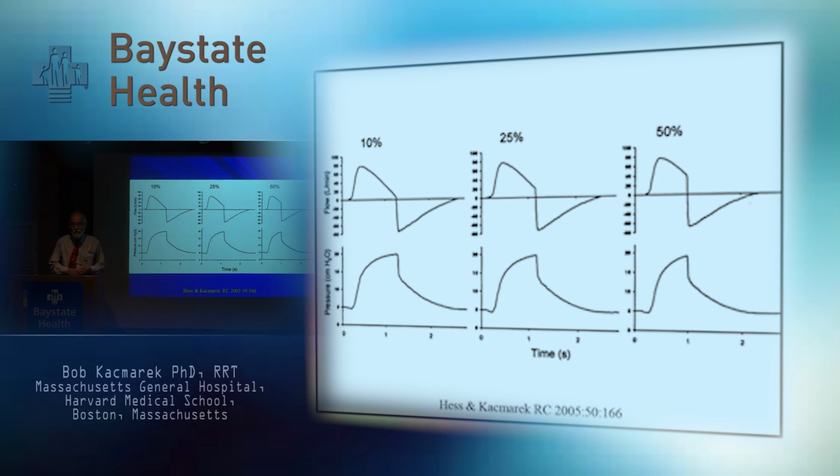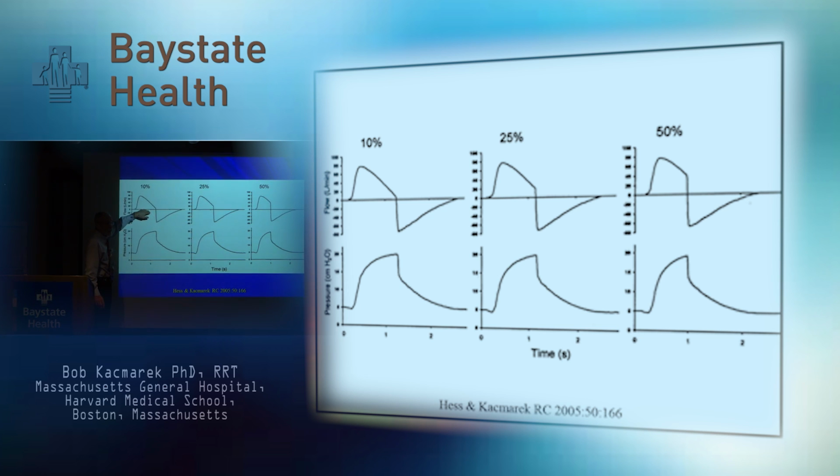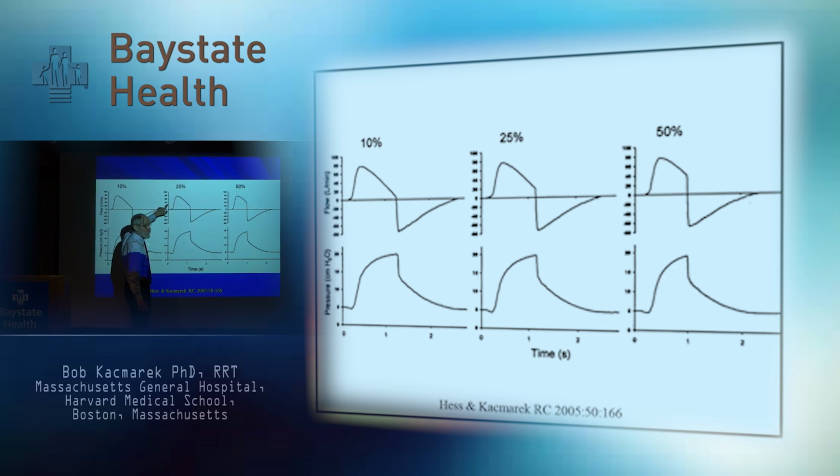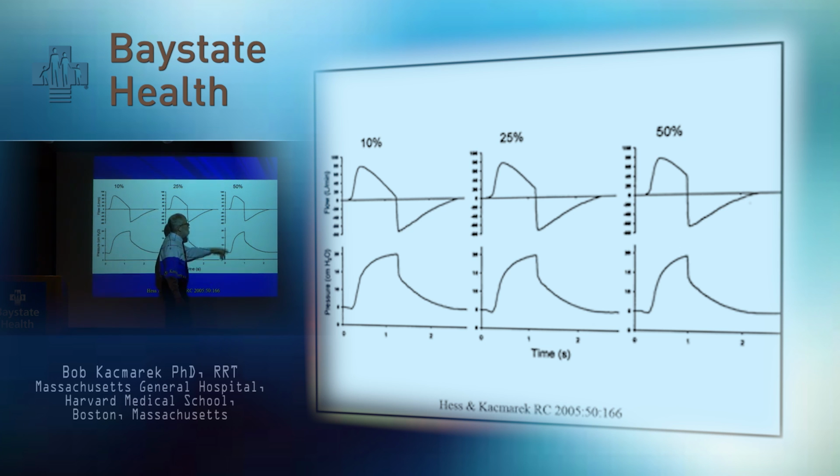So depending upon your ventilator, it's called eSense, termination criteria, expiratory cycling, different terminology used by different manufacturers to imply the same thing. A control that sets the percentage of the peak flow that terminates the breath. So if it's set at 10% and the peak flow is 80, when the peak flow drops down to 10, the breath ends. If I adjust it to 25, now when the peak flow goes to 25% of that, or in this case, 20 liters per minute. If I set it at 50%, when the peak flow goes down to 40, the breath ends.